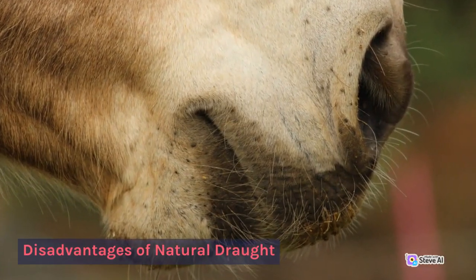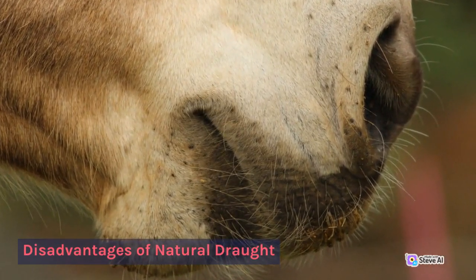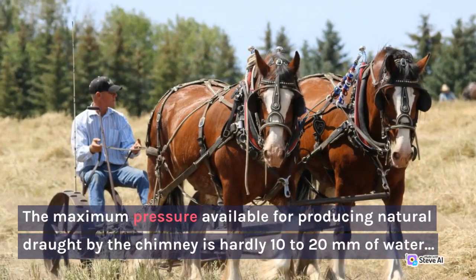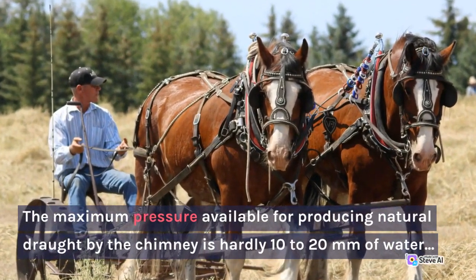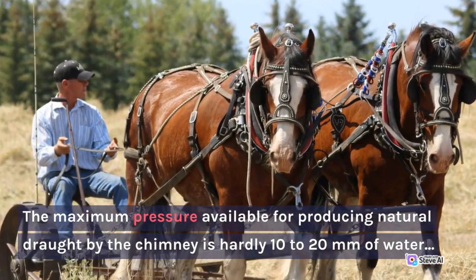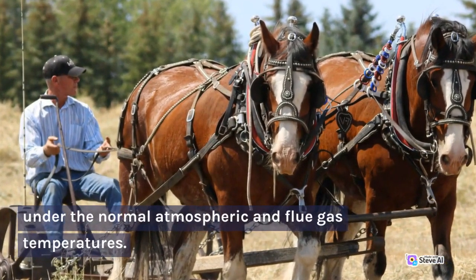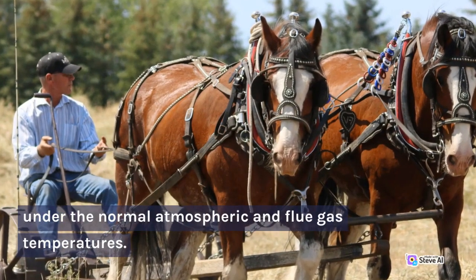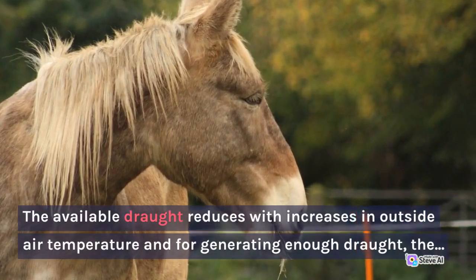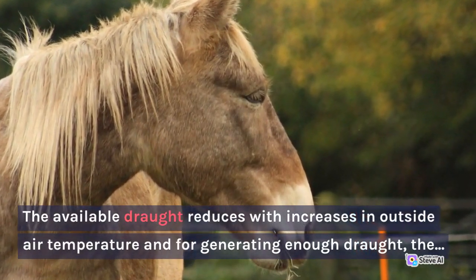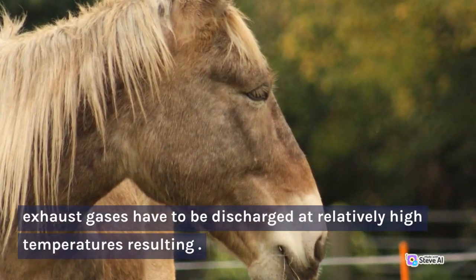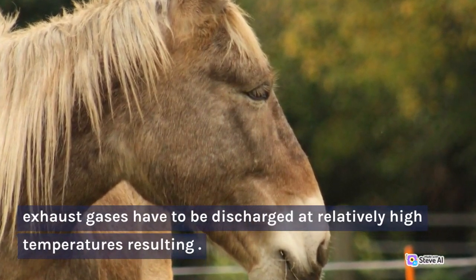Disadvantages of natural draft: the maximum pressure available for producing natural draft by the chimney is hardly 10 to 20 millimeters of water under the normal atmospheric and flue gas temperatures.